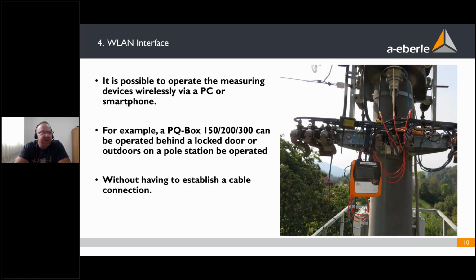A nice feature is a WLAN interface of all our boxes. So sometimes it's interesting to not open the cabinet and work remotely without establishing a cable connection directly with your device. Or you install a PQBox on a pole-mounted transformer station. You do not want to climb up, so it's easy to read out and to communicate with the PQBox wireless.